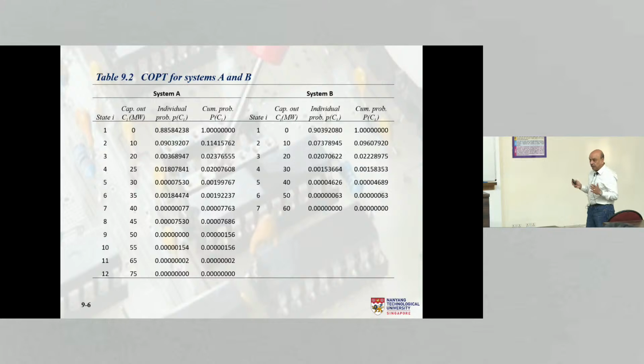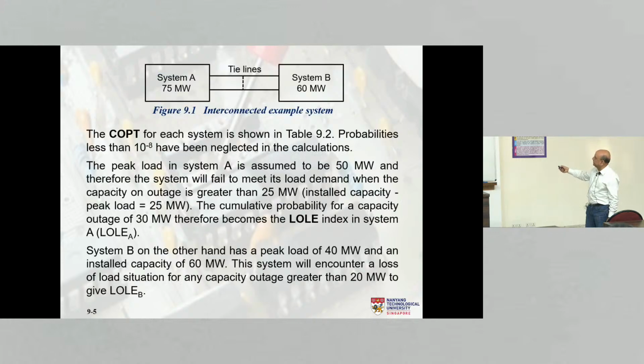Cumulative probability tells us that for 30 or more megawatt out, this is the cumulative probability, right? And that's my risk in the system, because up to 25 megawatt I don't lose any load, so I don't need to worry. But anything beyond that, I need to worry. This is the risk. Similarly, what's the risk in system B? The system B capacity is 60 megawatt and the load in system B is, where is that? 40, okay, if you say so. Yeah, peak load is 40.